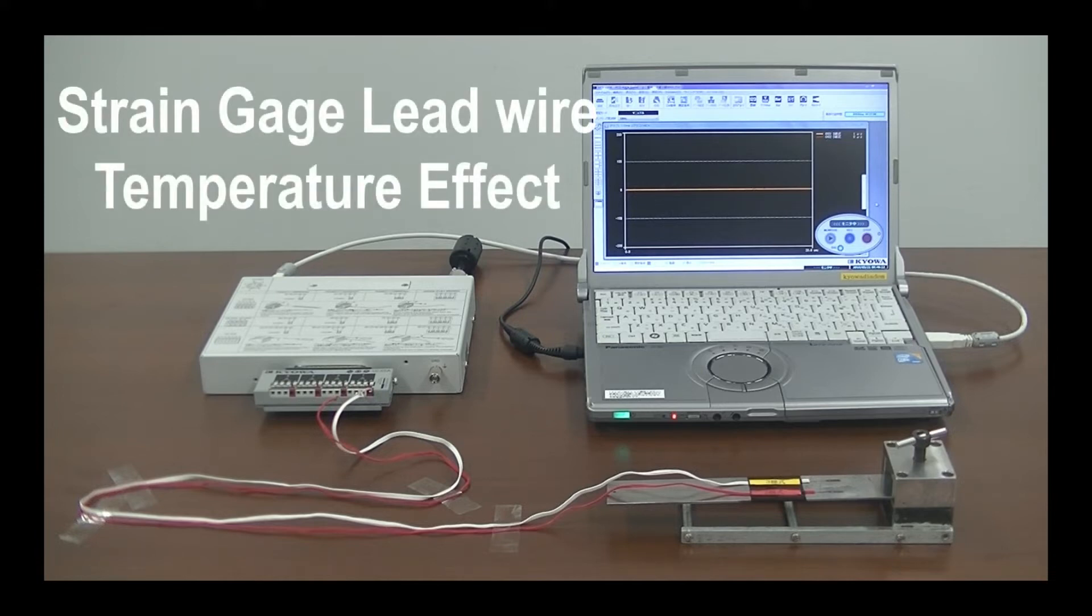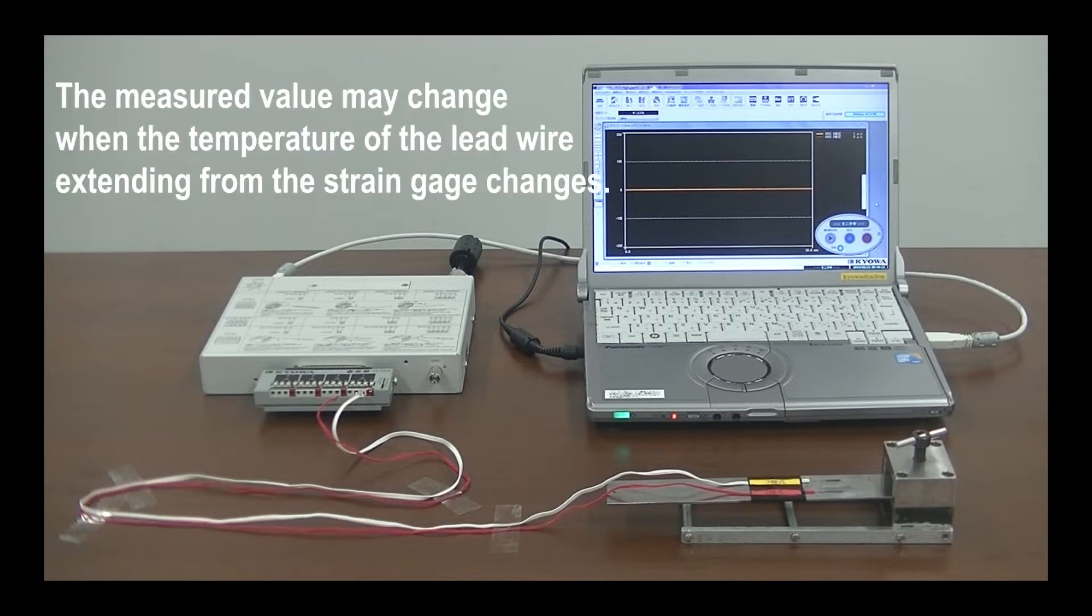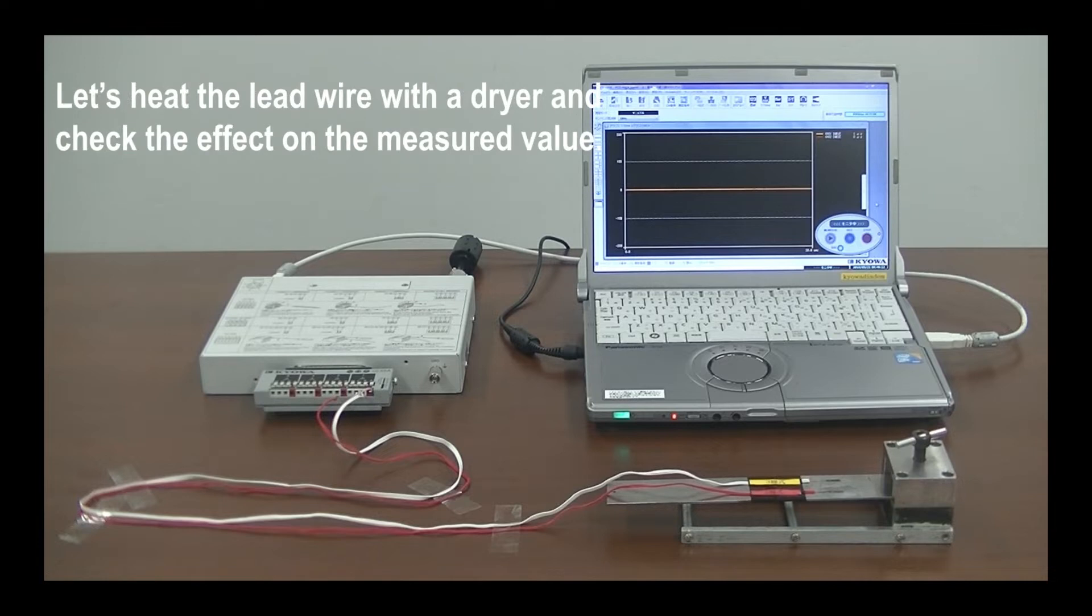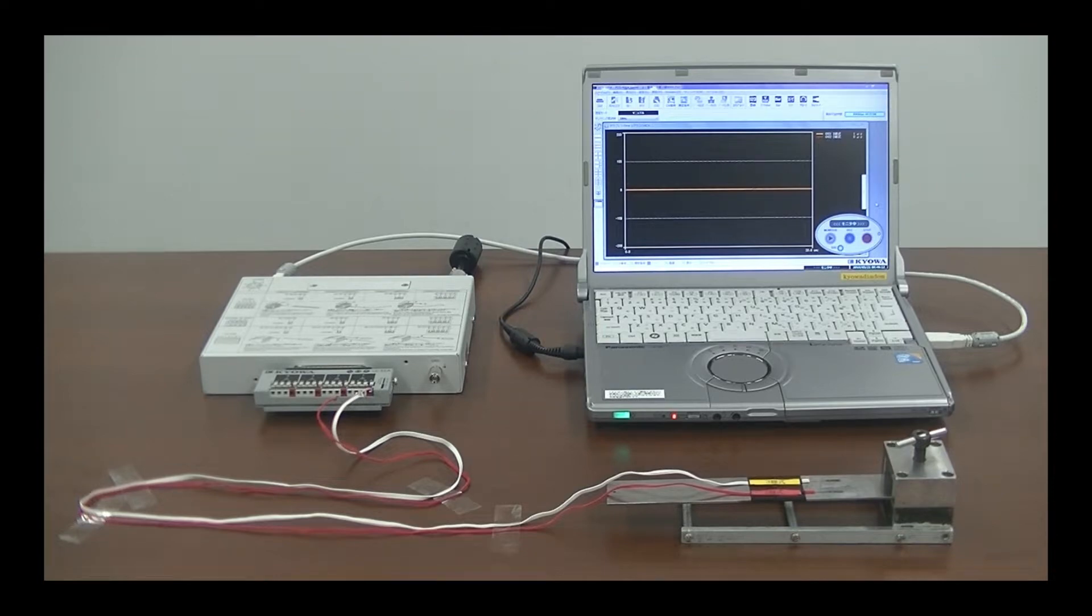Using just two wires might seem to be the obvious way to connect a strain gauge circuit. However, changes in temperature will affect the measurement accuracy in two ways. Firstly, the gauge application point will expand and contract with change in temperature. Secondly, the lead wire will change resistance with temperature. The three-wire circuit can help with this.